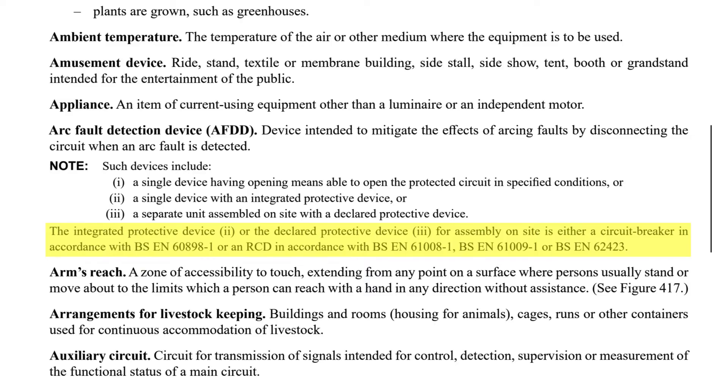The integrated protective device two or the declared protective device three for assembly on site is either a circuit breaker in accordance with BSEN 60898-1 or an RCD in accordance with BSEN 61008-1, BSEN 61009-1 or BSEN 62423.